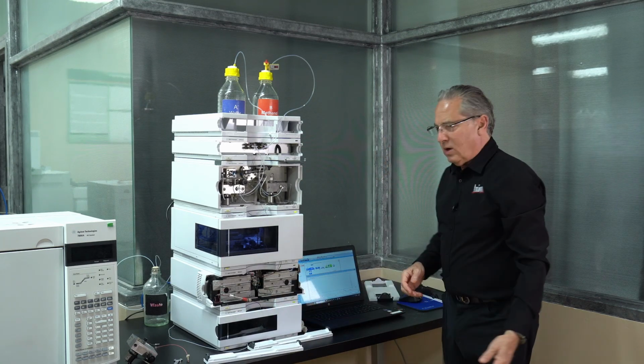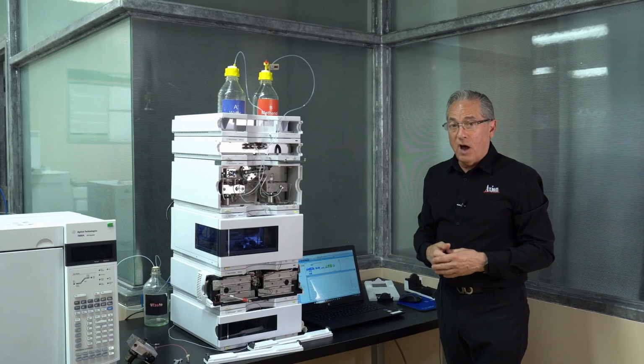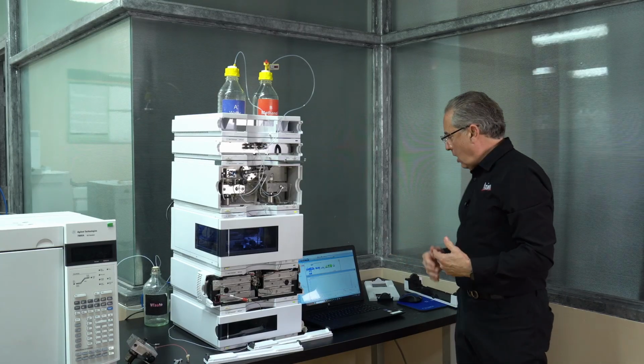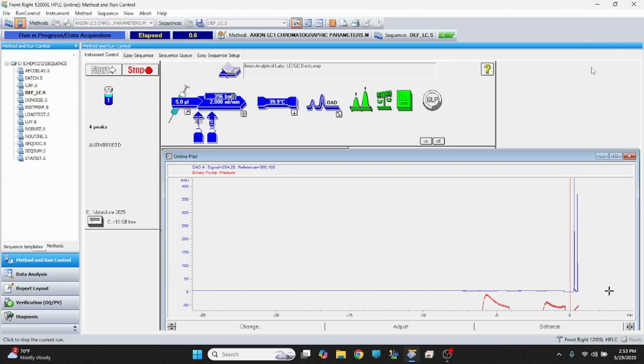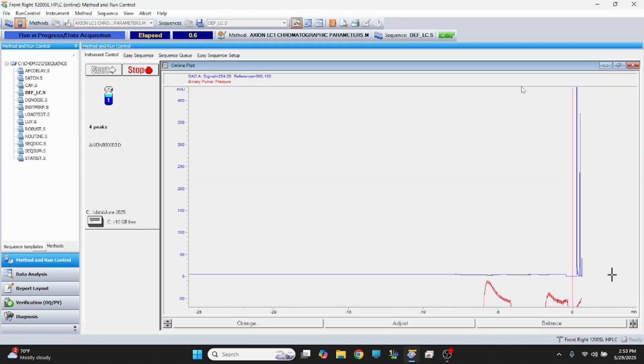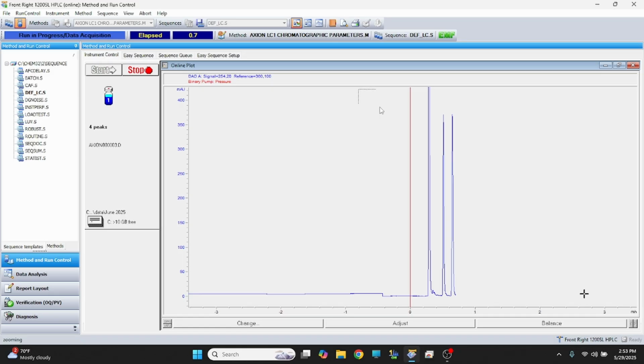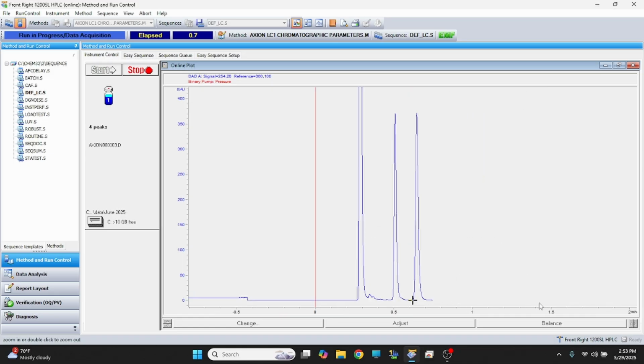Now in this case, we are not looking at the red and the blue coming off, just like in the Kool-Aid experiment, but our detector is seeing everything coming off. So as we look at our chromatogram, I'm just going to zoom in on this portion of it, we can see that in this case, I have a void volume marker, the T0 marker, and then I have 3 peaks of interest. And we see the first 2 have come out, waiting for the third one, and there's the third one. So when we look at the chromatogram, we're looking for a nice flat baseline.